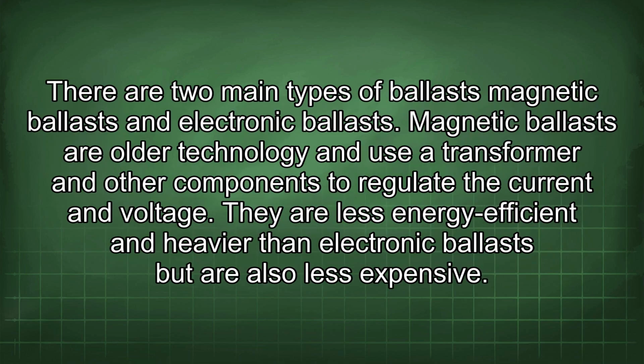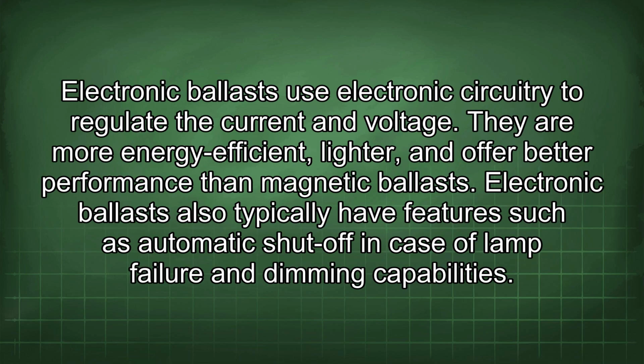There are two main types of ballasts: magnetic ballasts and electronic ballasts. Magnetic ballasts are older technology and use a transformer and other components to regulate the current and voltage. They are less energy efficient and heavier than electronic ballasts, but are also less expensive. Electronic ballasts use electronic circuitry to regulate the current and voltage. They are more energy efficient, lighter, and offer better performance than magnetic ballasts. Electronic ballasts also typically have features such as automatic shut-off in case of lamp failure and dimming capabilities.